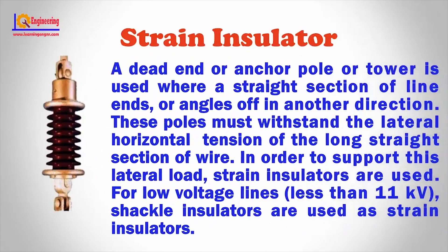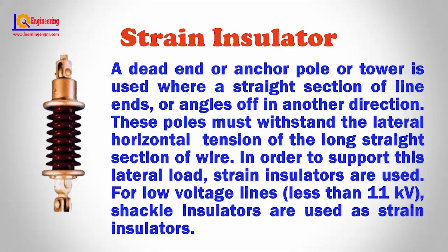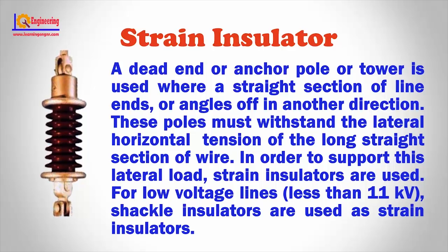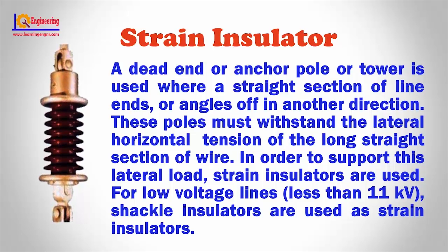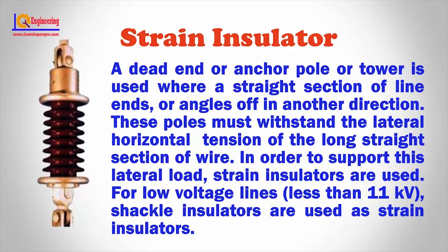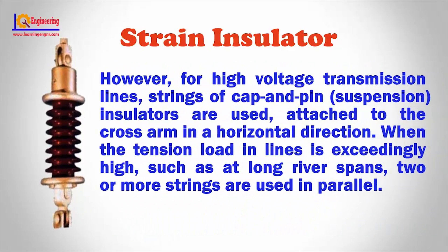Strain insulator: A dead end or anchor pole or tower is used where a straight section of line ends or angles off in another direction. These poles must withstand the lateral horizontal tension of the long straight section of wire. In order to support this lateral load, strain insulators are used. For low voltage lines less than 11 kV, shackle insulators are used as strain insulators. However, for high voltage transmission lines, strings of cap and pin suspension insulators are used, attached to the cross arm in a horizontal direction. When the tension load is exceedingly high, such as at long river spans, two or more strings are used in parallel.